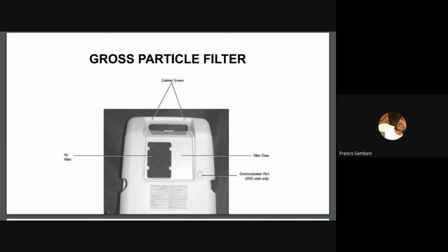And prior to use, if you have the time, you're supposed to wait for about 10 minutes, as it takes a little while for the device to concentrate to almost pure oxygen. It's not that the same moment you turn on the oxygen concentrator, you get the almost pure oxygen that you're looking for. So it takes a little bit of time. And now we'll proceed to look at the things that you're supposed to do while using the oxygen concentrator itself.